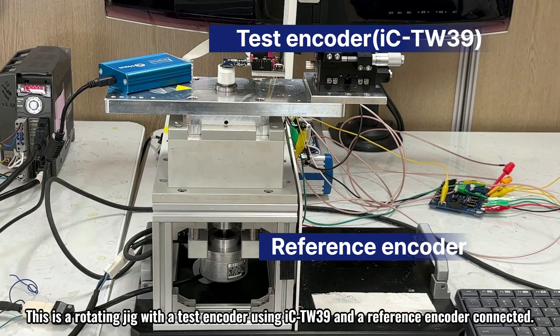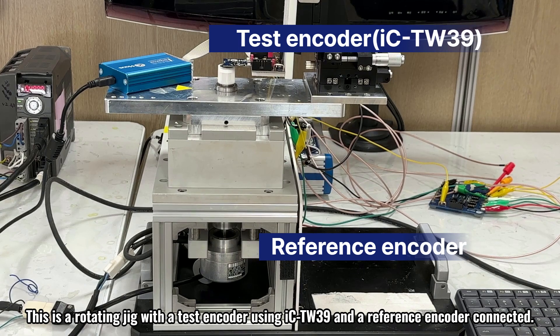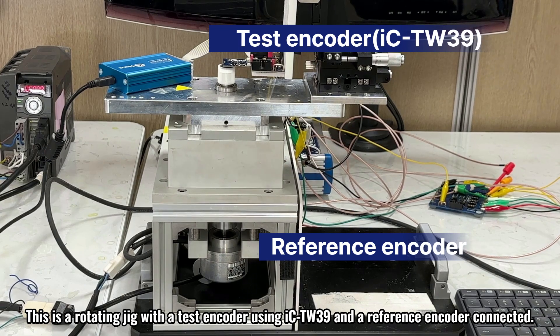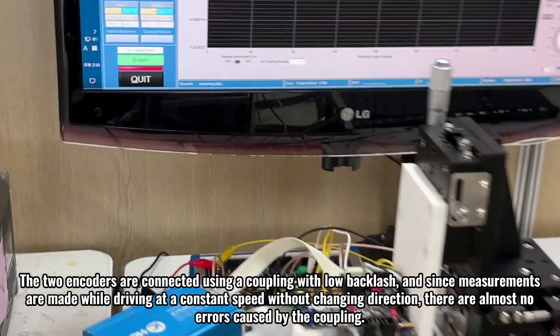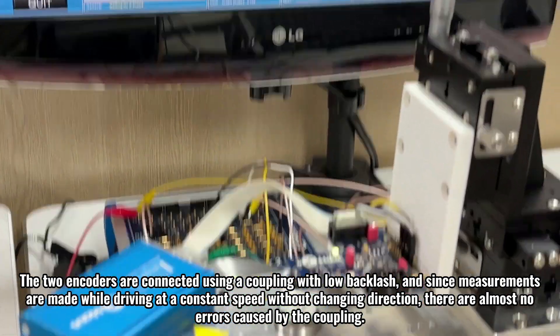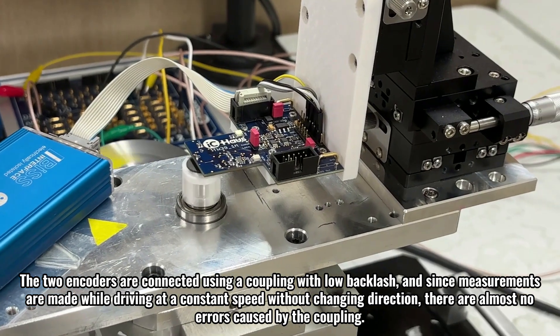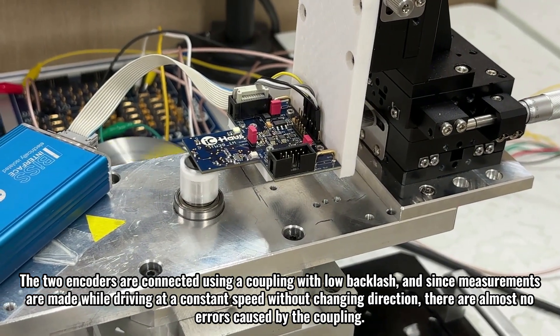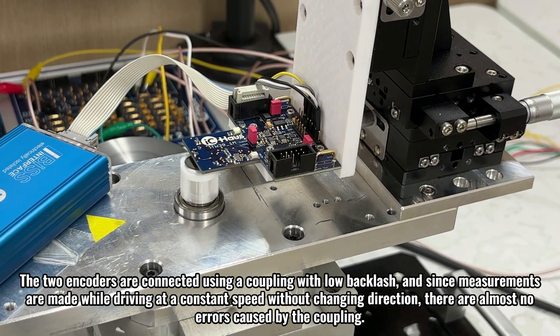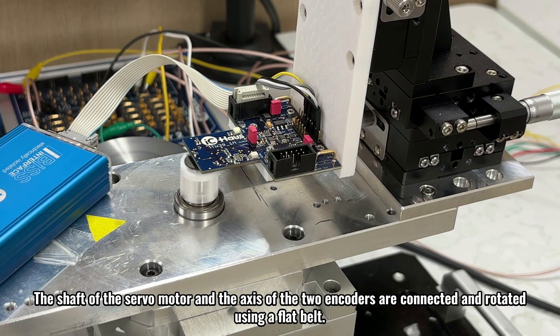This is a rotating jig with a test encoder using IC-TW39 and a reference encoder connected. The two encoders are connected using a coupling with low backlash, and since measurements are made while driving at a constant speed without changing direction, there are almost no errors caused by the coupling. The shaft of the servo motor and the axis of the two encoders are connected and rotated using a flat belt.